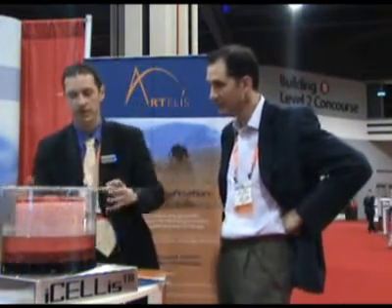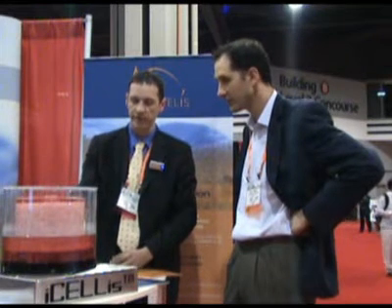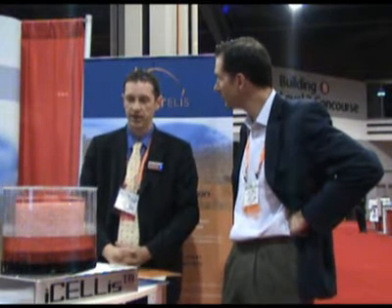The way the bioreactor works, we have fibers or carriers where the cells grow in adherence in what we call the fixed bed. This is the central part of the inner cylinder of this bioreactor, and the cells grow there at very high cell densities. We have a centrifugal pump allowing the liquid to go up into the bed, going down along this falling film to be oxygenated again, so we don't need a sparger. The bioreactor will be supplied pre-sterilized and ready to use and can be disposed after use.